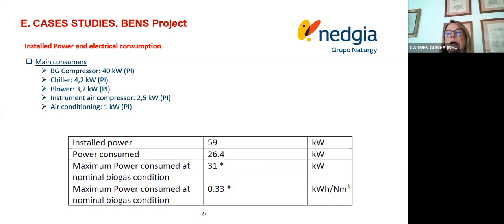This plant can work normally from 50 to 100% of the nominal capacity. With flows under 50%, the electrical consumption is much higher because the compressor cannot work with the frequency converter. Therefore, the electrical consumption is higher.